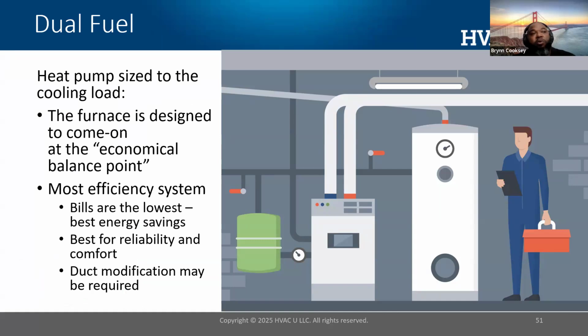And my personal favorite is dual fuel. Dual fuel is a furnace and heat pump combination where the heat pump is the primary source, and either the heat pump taps out on capacity or my savings is lost because of the temperature outside and the cost of my fuel, and I can turn the heat pump off and bring on my gas furnace. This is one of the best options because I can run electrification for a large amount of the time during the year and only rely on my gas furnace when it gets really cold or my rates are high. Duct modification may or may not be required depending on how you size it, but this is one of the ways where you can split the difference, have the backup of gas fuel, but also participate in electrification projects.